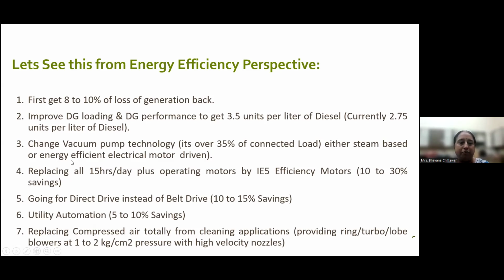Then we can improve the DG loading and DG performance, to get 3.5 units per liter of diesel. Then change the vacuum pump technology, that is 35% of the connected load, either steam based or energy efficient electrical motor driven. Then replace all motors operating 15 hours per day plus with IE5 energy efficiency motors.